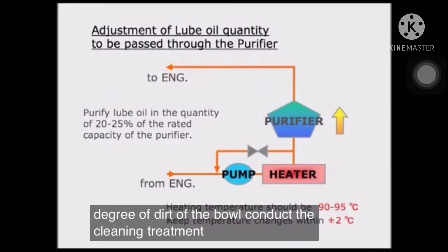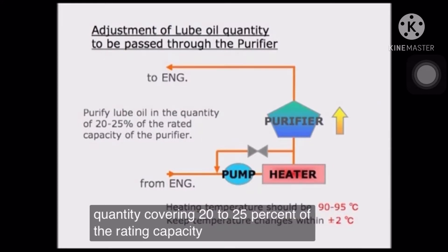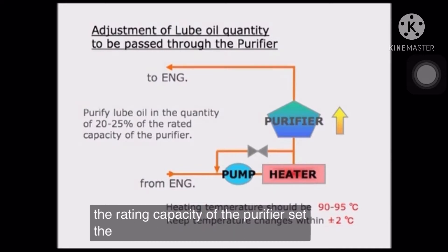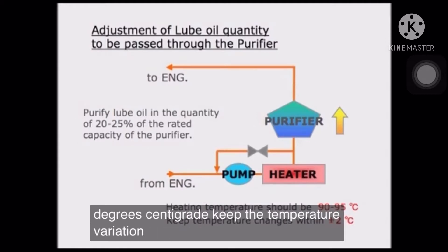Conduct the cleaning treatment with the feeding oil quantity covering 20 to 25% of the rating capacity of the purifier. Set the heating temperature at 90 to 95 degrees centigrade, and keep the temperature variation within plus or minus 2 degrees.